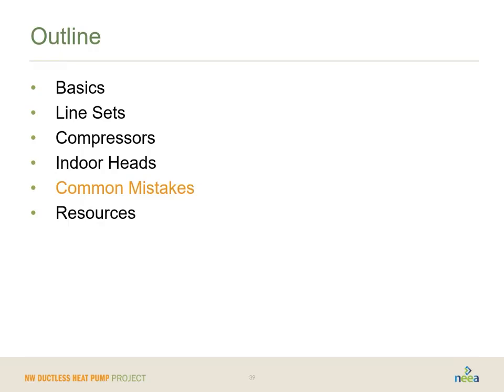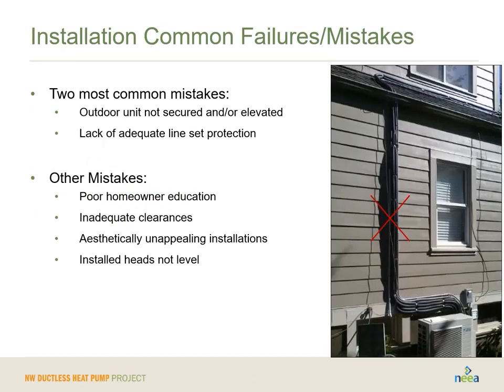Now let's talk a little bit about common mistakes that we see with ductless heat pump installations. There are some real common things. Again, I mentioned earlier, maybe the most common thing is not having proper expectations or homeowner education, but there are some other things we see. The outdoor unit not being secured or elevated in areas of snow and not being level are really common problems. And it's a good way to make sure that you fail a quality assurance site visit. So take care of that. It will improve the longevity of the equipment and make sure that it works correctly.